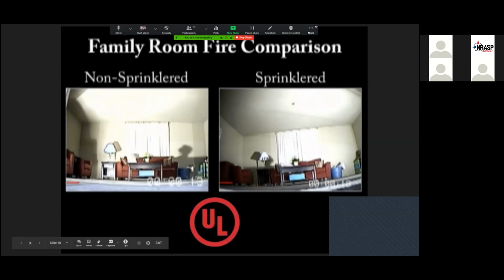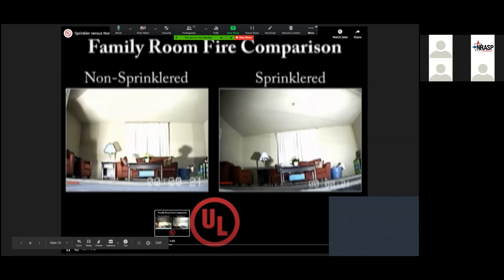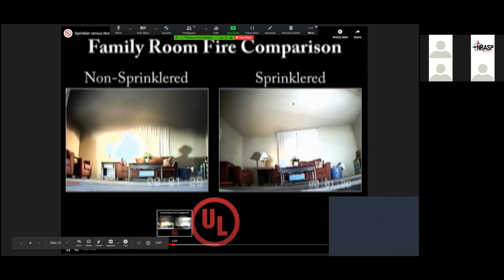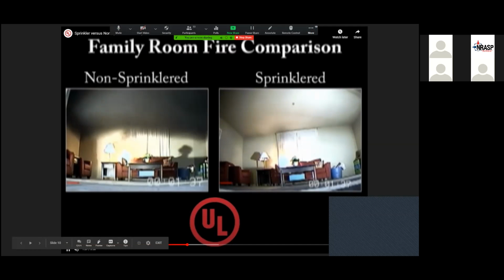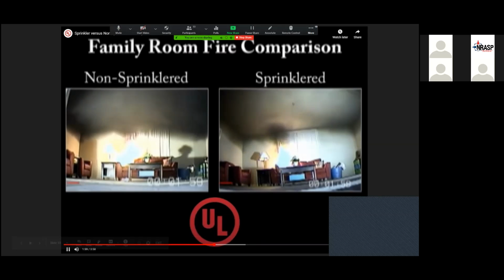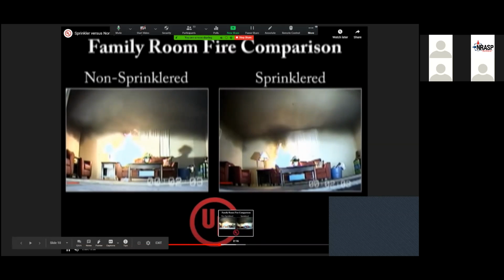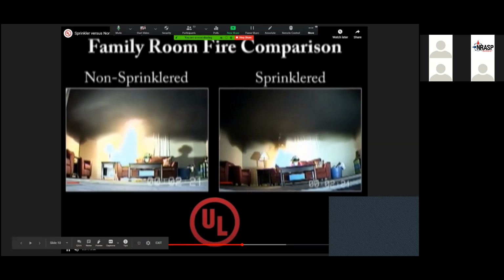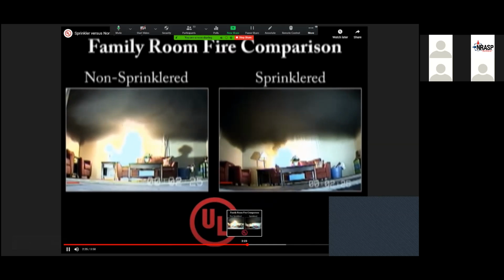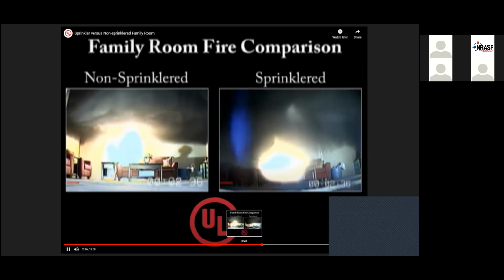And I'm going to speed it ahead because I realize that we're already past 11:30, so I'm going to bump this video ahead because it's just going to be watching the fire grow here for a while. And I think when we get to about 2 minutes and 30 seconds, you'll see the fire sprinkler system go. So I'm going to bump us ahead a little bit here, and we'll just watch for a few seconds on the right. Shortly here, you're going to see that fire sprinkler system activate. Right there, it activated. And you're going to see that fire dampen down and see how it brings that back in check. So it's going to hold it to that position or possibly extinguish it by the time we get there.